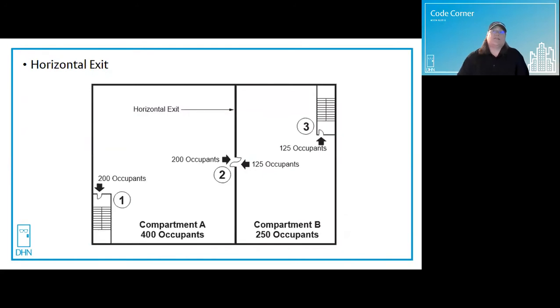A horizontal exit is an exit component consisting of fire resistance rated walls, floors and ceilings, and fire rated door openings. It is intended to compartmentalize portions of a large building into smaller compartments of no more than 22,500 square feet, thereby creating refuge areas that afford safety from the fire and smoke from the area of fire origin.